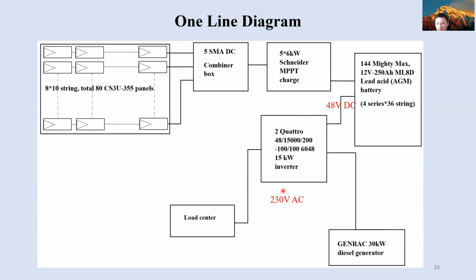We also have a 30 kilowatt diesel generator, and it operates if the battery state of charge drops to 50%. As I talked about already, the inverter automatically starts the generator and simultaneously supplies the load and charges the battery, and this inverter gives priority to the load first.